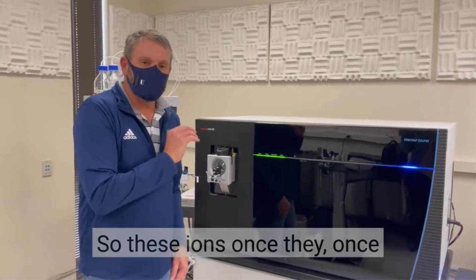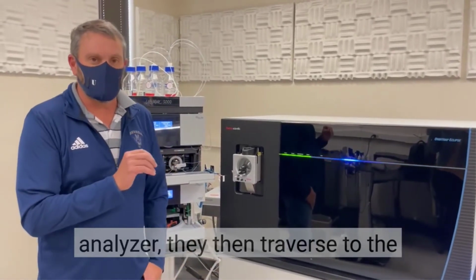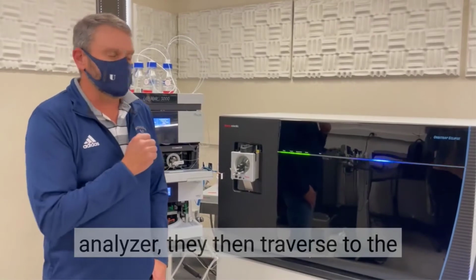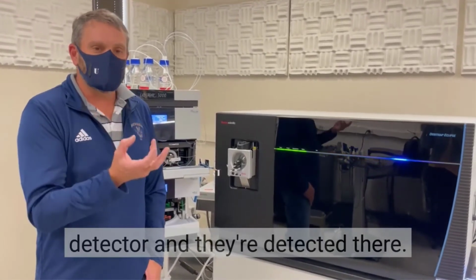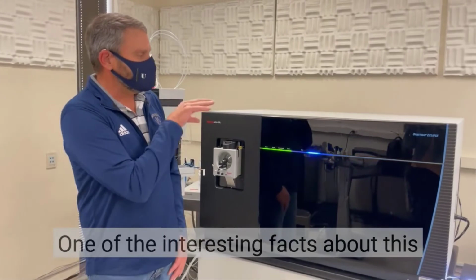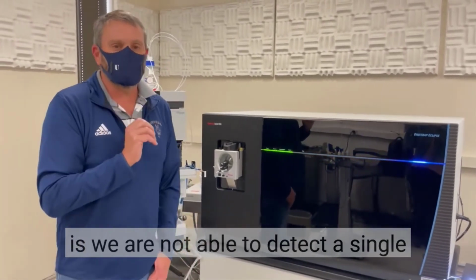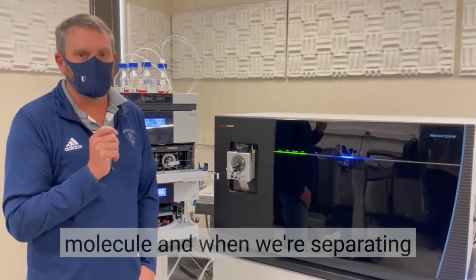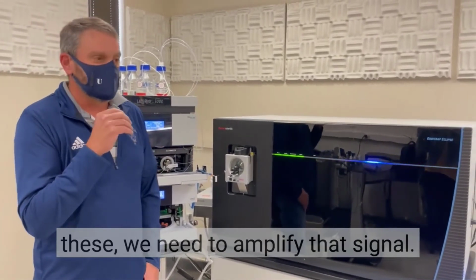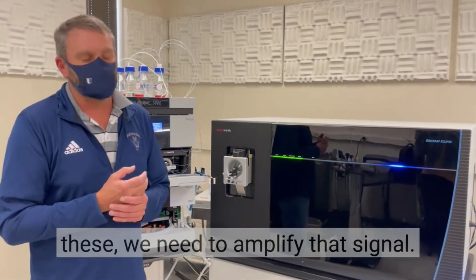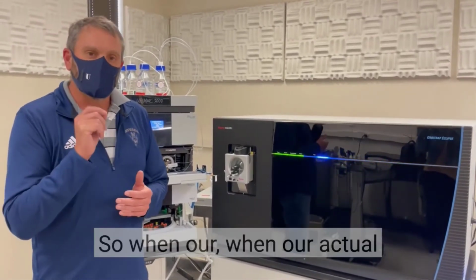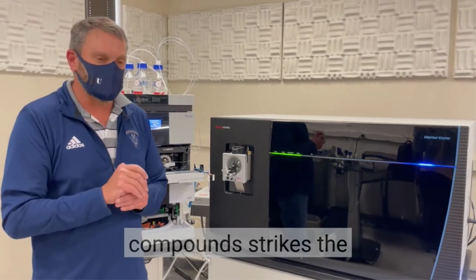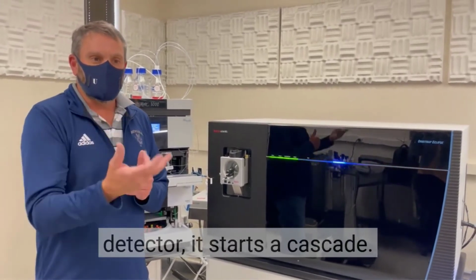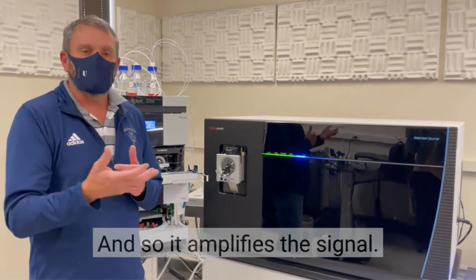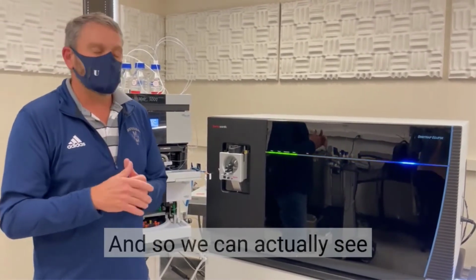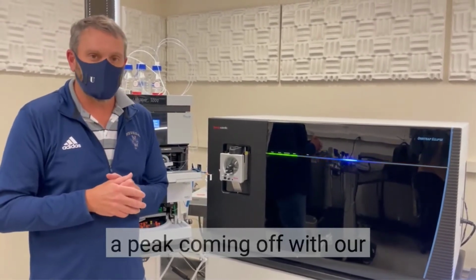So these ions, once they are separated by the mass analyzer, then traverse to the detector, and they're detected there. One of the interesting facts about this is we are not able to detect a single molecule. And when we're separating these, we need to amplify that signal. So we use an electron multiplier.